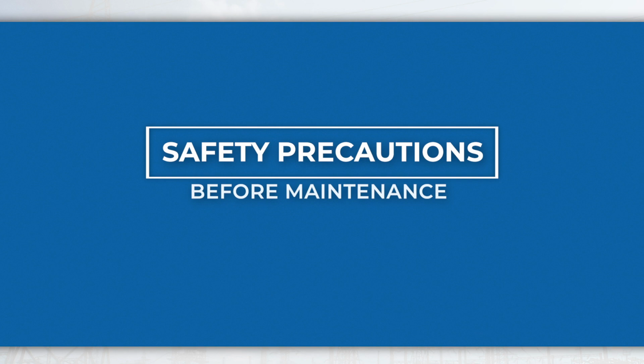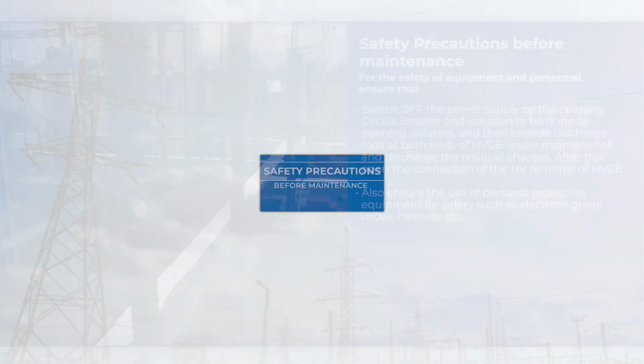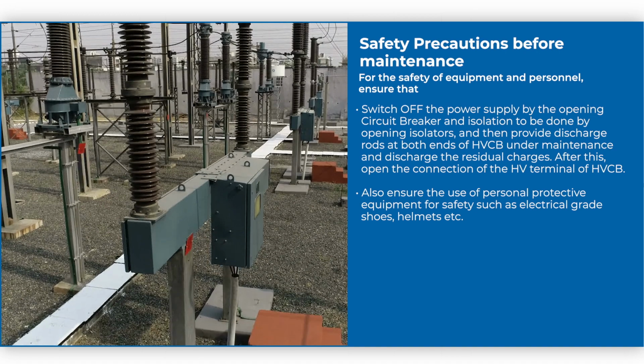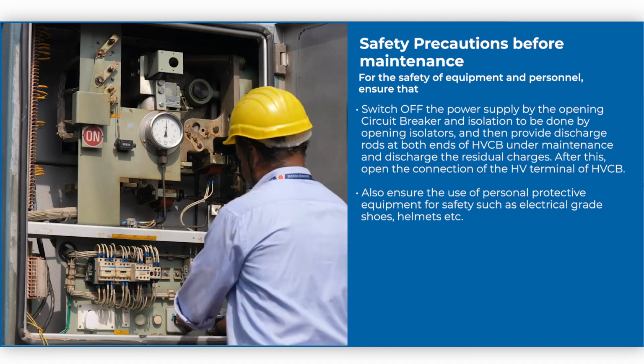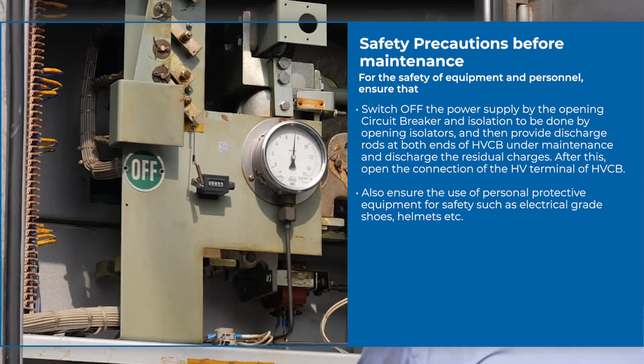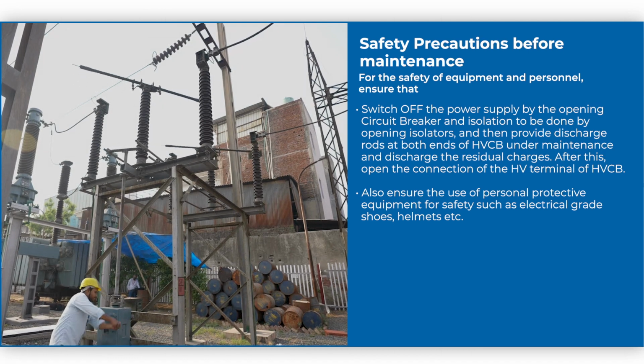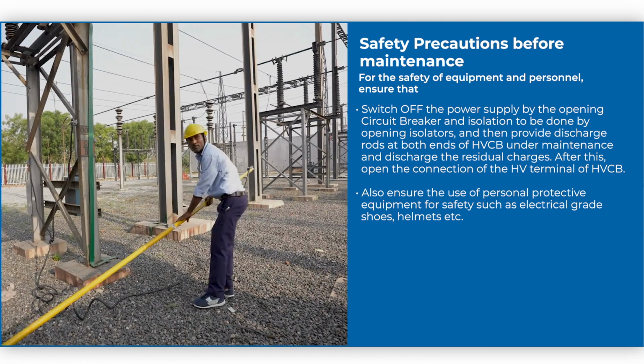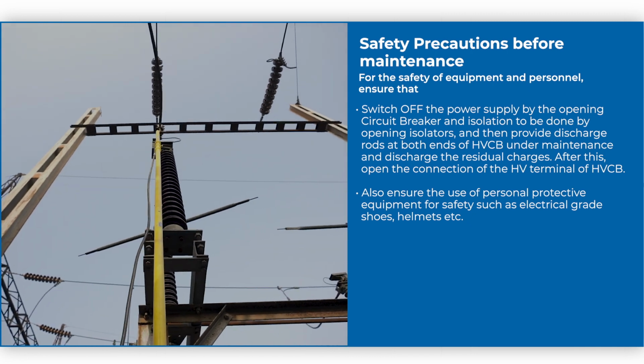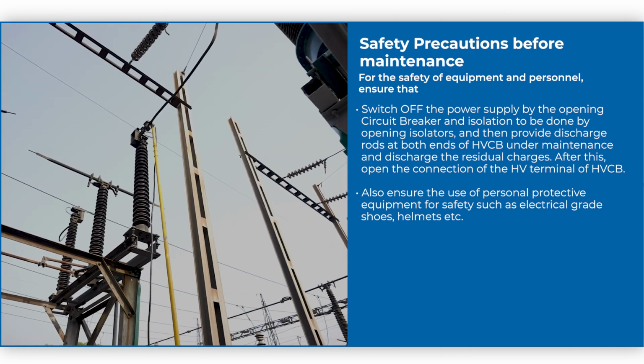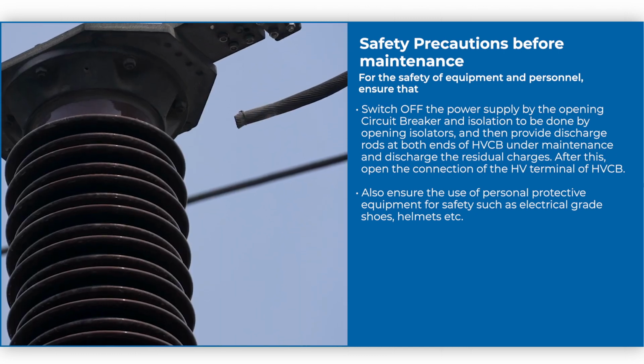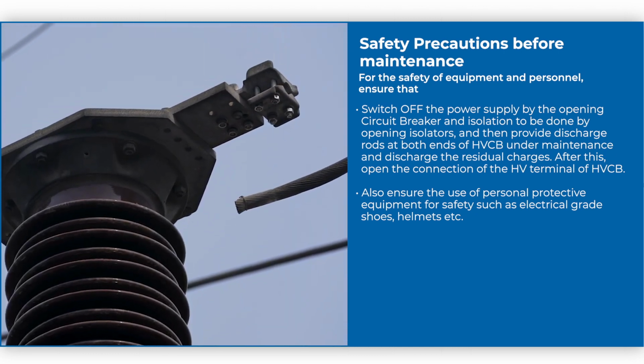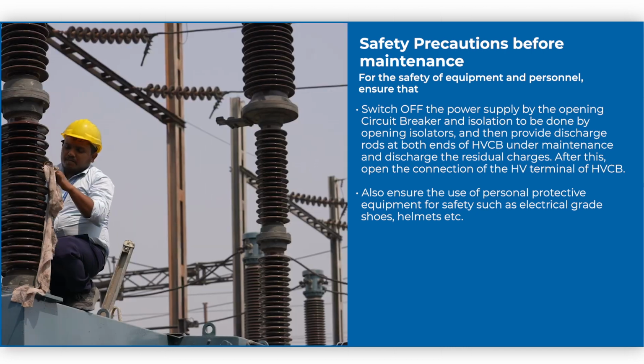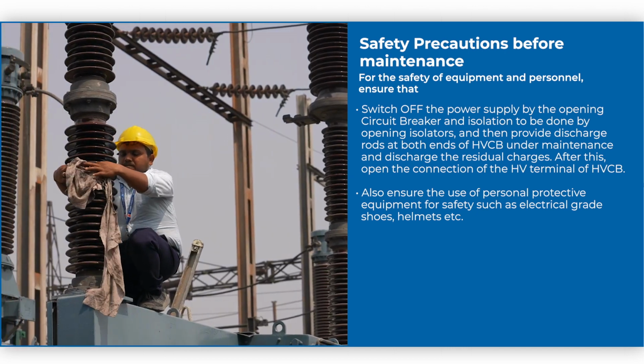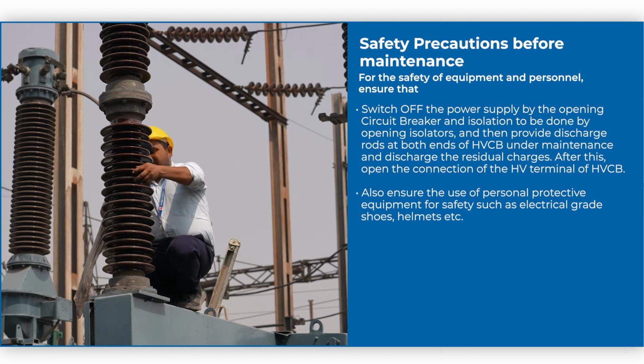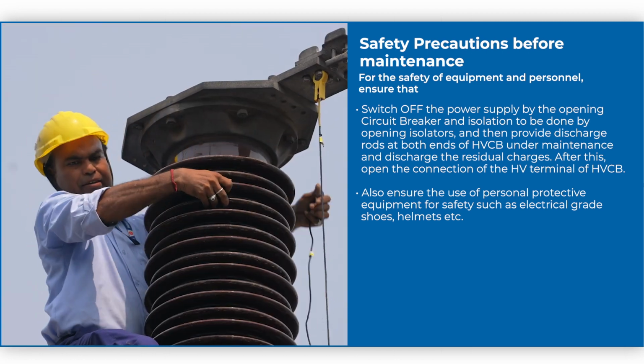Safety precautions before maintenance. For the safety of equipment and personnel, ensure that you switch off the power supply by opening circuit breaker, and isolation to be done by opening isolators, and then provide discharge rods at both ends of CB under maintenance and discharge the residual charges. After this, open all the HV side connections of CB, and also ensure the use of personal protective equipment for safety such as electrical grade shoes, helmets, etc.